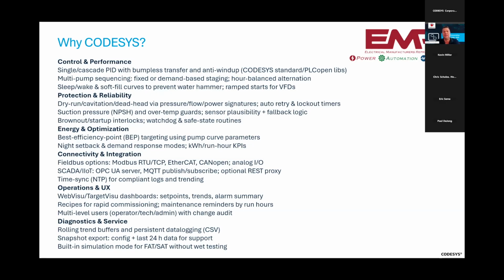Some of the reasons we use CODESYS, some of the things we're doing with this smart controller. So running PIDs, basically bumpless transfer. We got up to 4 booster pumps and up to 6 well sites and 2 valves in the same system. What it allows is load balancing. You've got water hammer prevention, all the things you're going to expect when you're trying to build a pump, booster station, or even a lift station. And as we have deployed these, we've got somewhere around 75 of these deployed right now in the field. We keep adding features that customers come back and say, well, it'd be nice to know if this one ran longer today than it did yesterday, or if the flow rate is different over a time period. So all those are new features we keep adding.